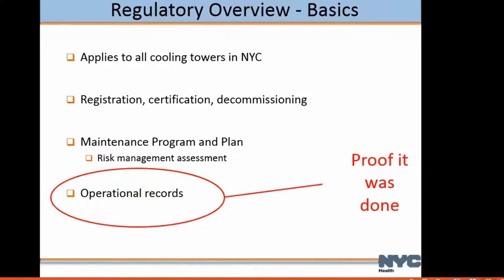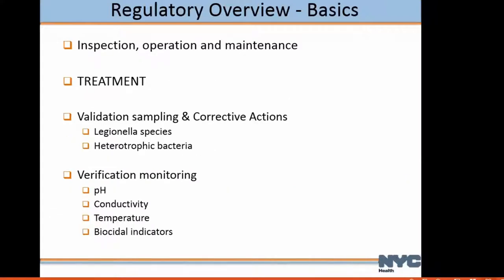The operational record is another big requirement — this is proof that what you said you were going to do in your plan, you actually did. You've got to write it down. What gets written down gets done; what gets measured gets done. The regulations also provided some minimums with regards to inspection, operation, and maintenance. Probably the biggest minimum is treatment — it required cooling tower systems to have treatment.